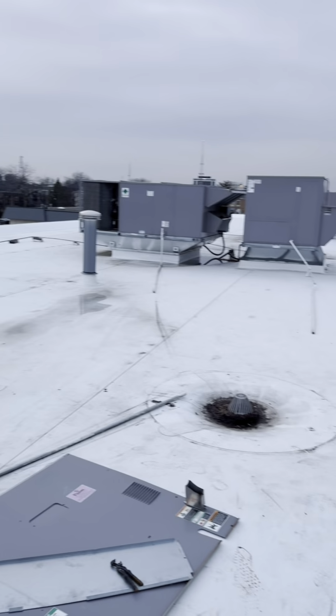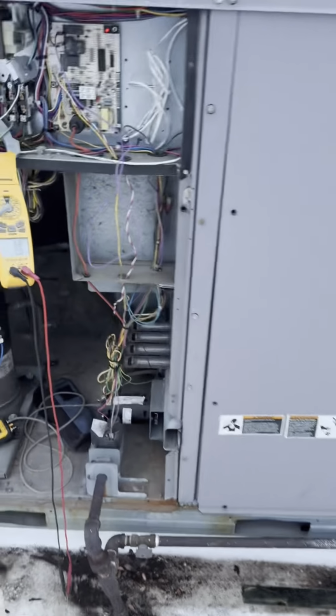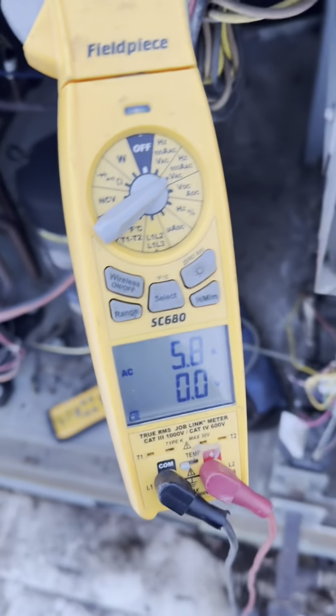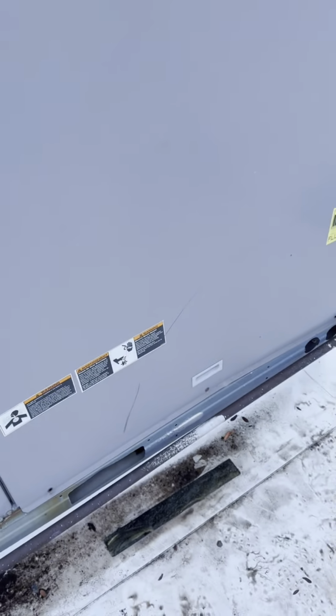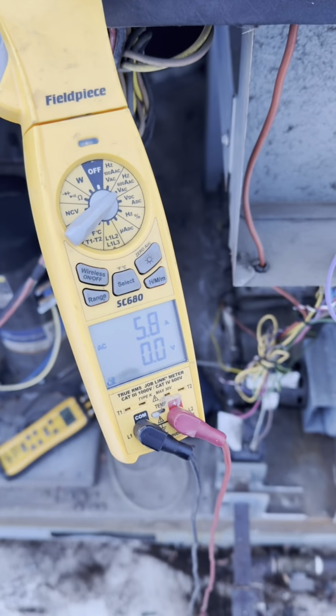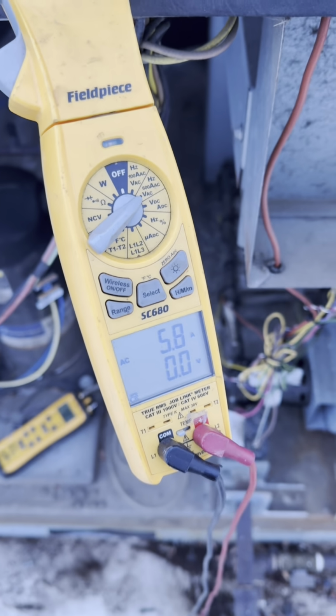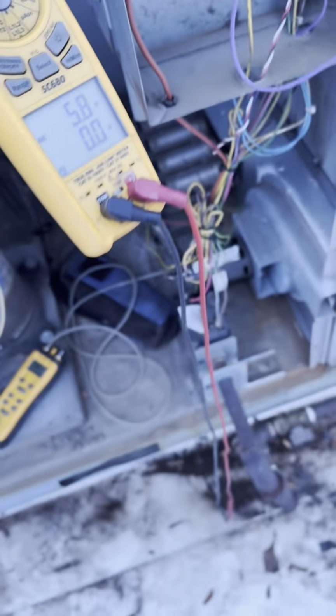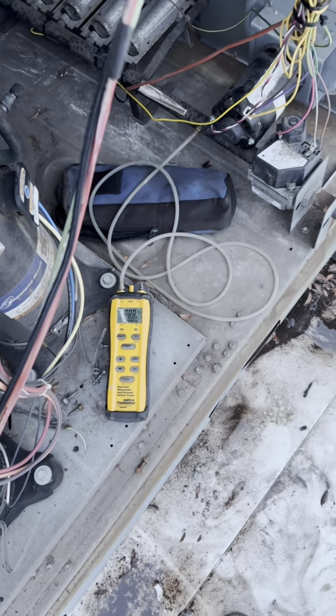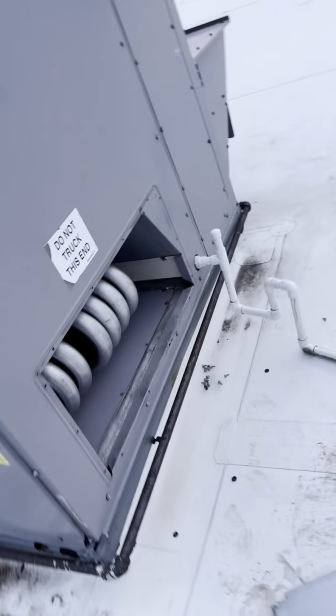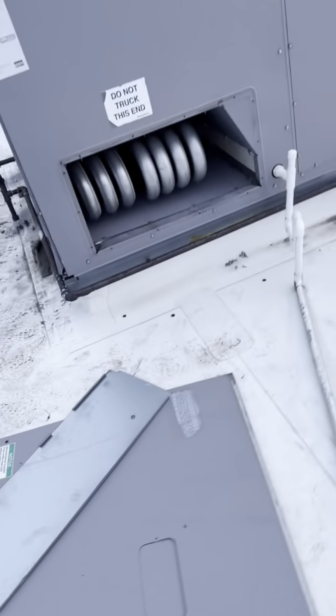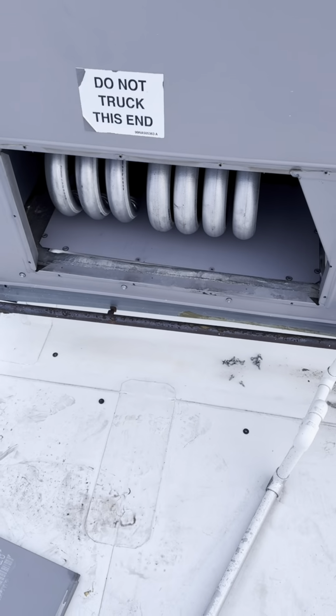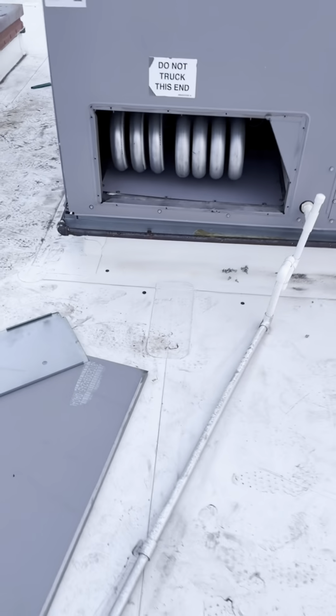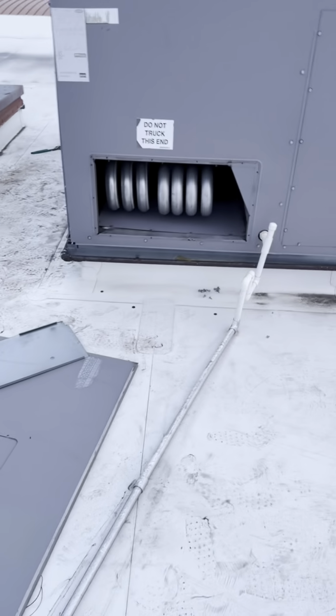I had to look at some other units here for the customer, but I'm back to this one to finish it up. My blower's back on. We are running at 5.8 amps, and the tolerance on the motor is 6.8, so we're good there. I have my manometer hooked up to the manifold to read the manifold pressure once the burners start, and the end cover removed and placed onto the discharge duct, so that the smoke from the heat exchanger burning off that oil does not get back into the building.